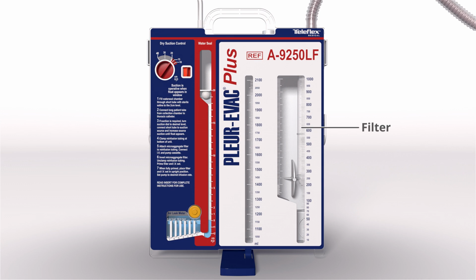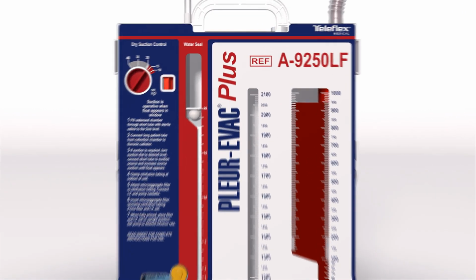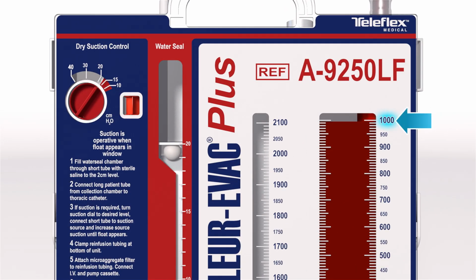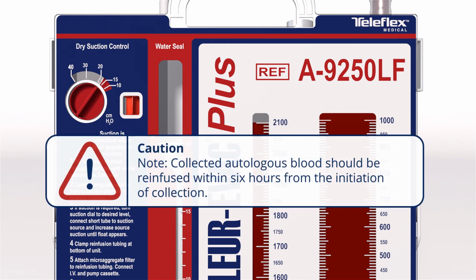Its purpose is to trap any clots or debris coming from the chest cavity while allowing maximum blood flow through the unit. When the fluid in the collection chamber exceeds 1,000 milliliters, the fluid will spill over into the second collection chamber. Blood cannot be recovered from the second chamber. It functions solely as a collection chamber. When drainage reaches 2,100 milliliters, the unit is filled to capacity and must be replaced. Note: collected autologous blood should be reinfused within 6 hours from the initiation of collection.